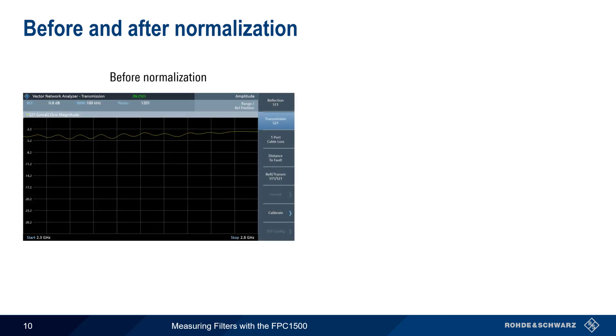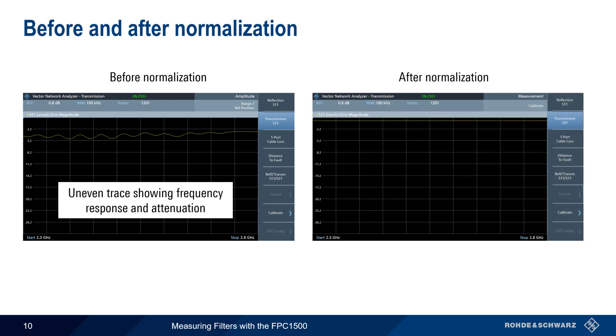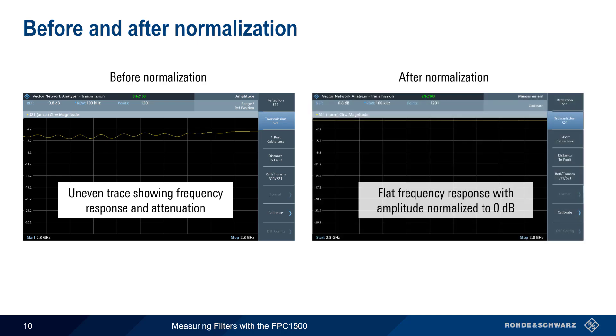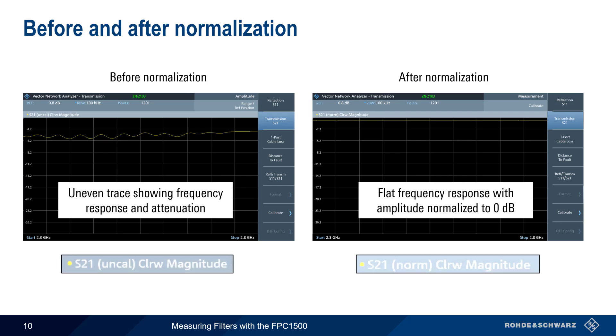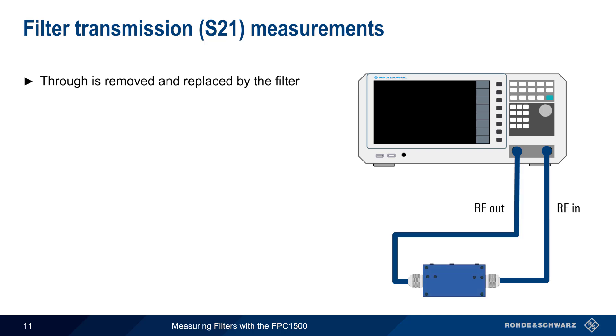Here is a typical display before normalization. Although the tracking generator output is constant, the frequency response and attenuation of the cables will create an uneven or wavy trace. After normalization has been run, the line should be flat and the level of this line should be normalized to 0 dB. All filter transmission measurements will now be relative to this level. Note that the calibration status is shown on the upper left portion of the screen — 'Uncal' means uncalibrated and 'Norm' indicates that normalization has been performed for the configured frequency range. After normalization, the through is removed and replaced by the filter under test.